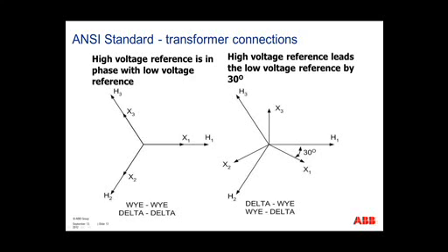If you have a Delta-wye or a Wye-Delta connected transformer, there is going to be a 30-degree phase shift. And the phase shift will be that the high side will always lead the low side by 30 degrees, no matter if it's a Delta-wye or a Wye-Delta connected transformer, and we'll see that in the next couple slides.